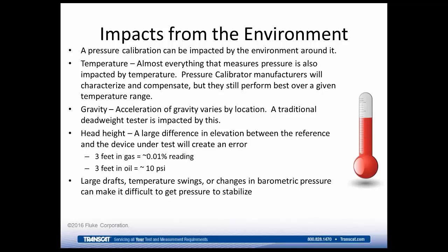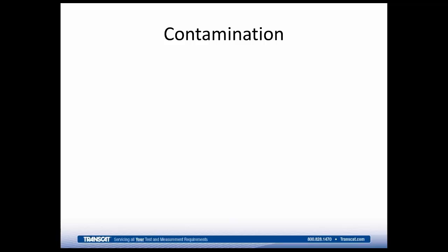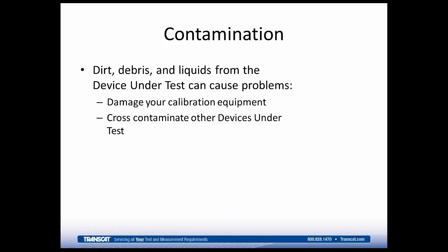Large drafts, temperature swings, or changes in barometric pressure can make it difficult to get pressure to stabilize. And that's a huge thing that we need to consider when we're looking at the environment that we're doing our calibration in. Another thing to consider is contamination. Dirt, debris, and liquids from the device under test can cause problems. They can damage your calibration equipment, it can cross-contaminate other devices under test, and just play havoc in your overall system.